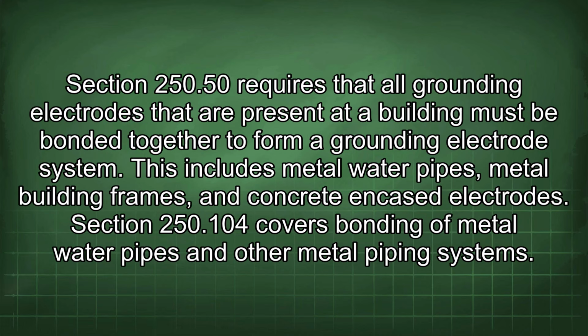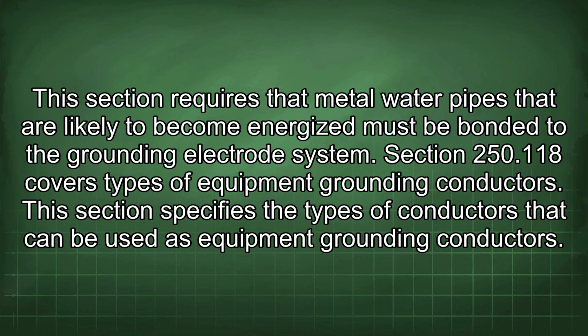Section 250.50 requires that all grounding electrodes that are present at a building must be bonded together to form a grounding electrode system. This includes metal water pipes, metal building frames, and concrete encased electrodes. Section 250.104 covers bonding of metal water pipes and other metal piping systems. This section requires that metal water pipes that are likely to become energized must be bonded to the grounding electrode system.